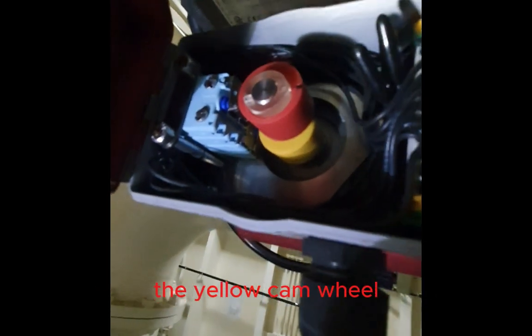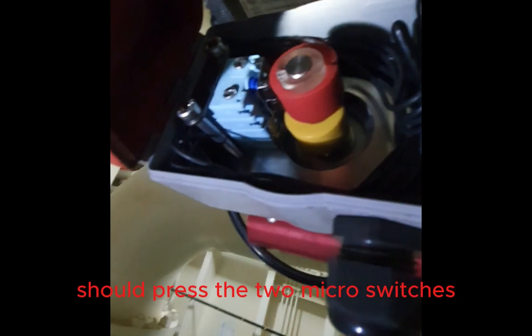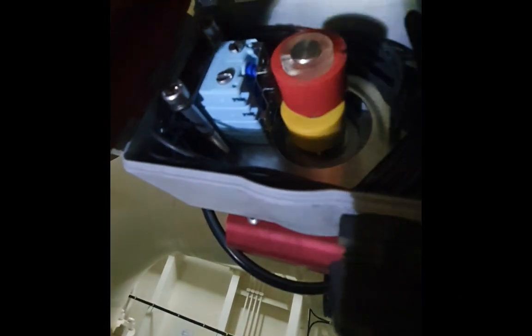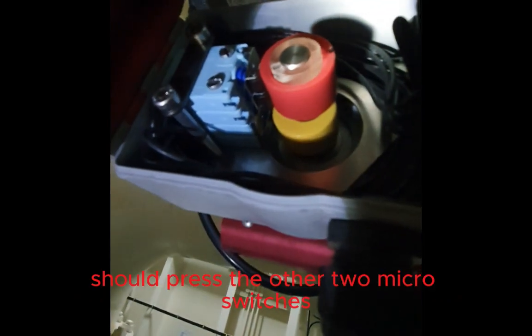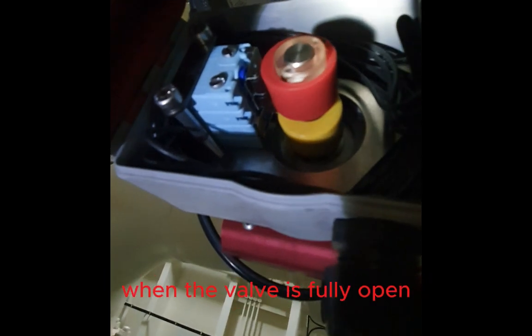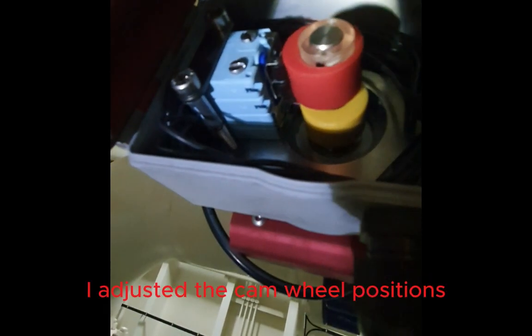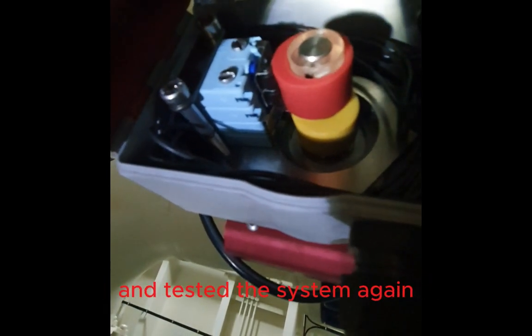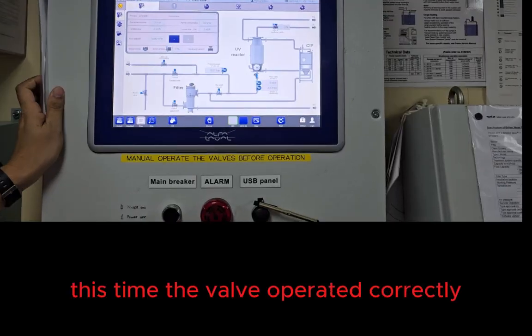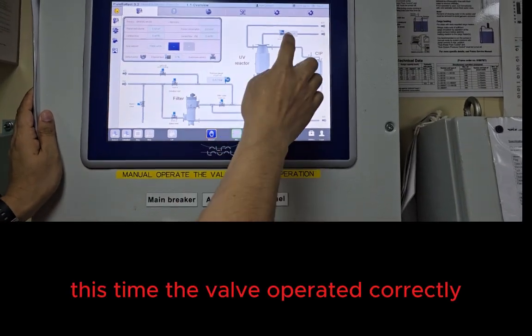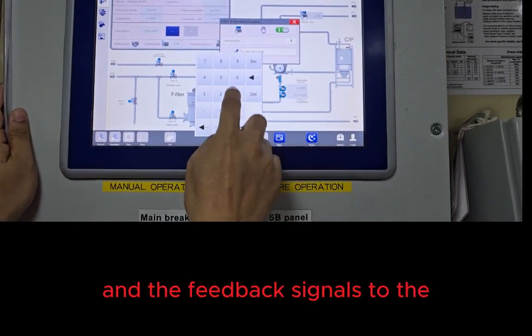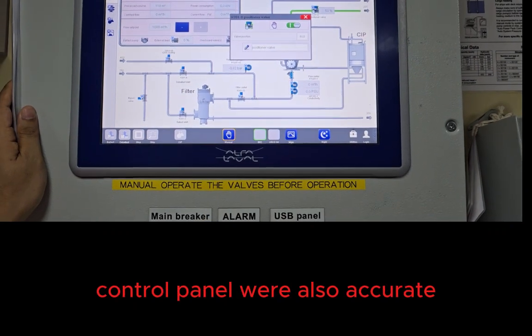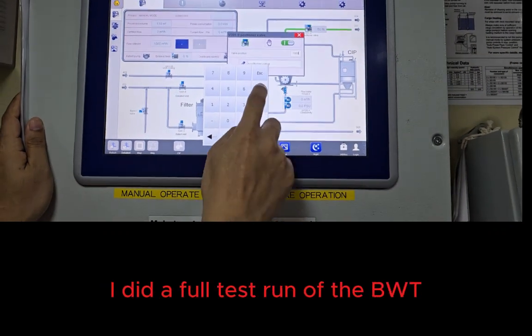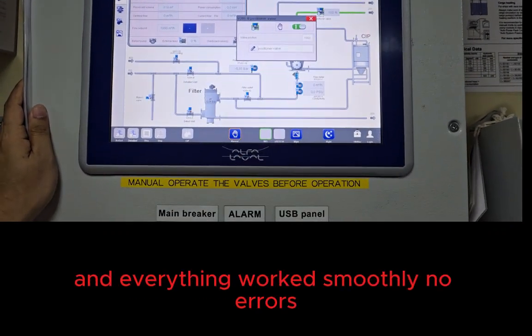The yellow cam wheel should press the 2 micro switches when the valve is fully closed, and the red cam wheel should press the other 2 micro switches when the valve is fully open. I adjusted the cam wheel positions and tested the system again. This time, the valve operated correctly, and the feedback signals to the control panel were also accurate. I did a full test run of the BWTS and everything worked smoothly, no errors.